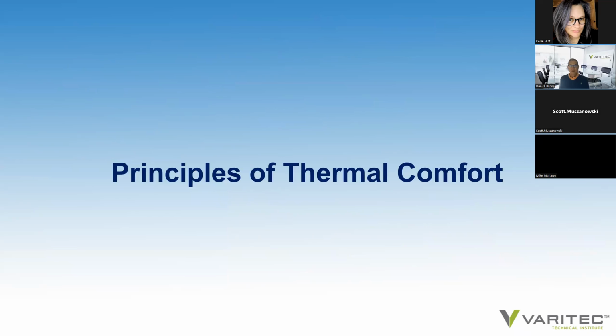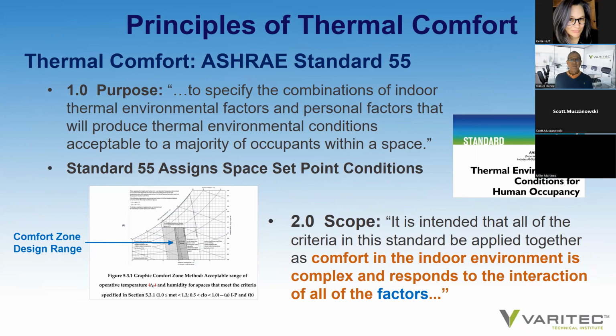So, that being stated, what are these principles of thermal comfort that ASHRAE Standard 55 promotes? Well, Standard 55's purpose in the opening documents of the standard states that its purpose is to specify the combinations of indoor thermal environmental factors and personal factors that will produce thermal environmental conditions acceptable to a majority of occupants within a space. Standard 55 assigns space set point conditions that are adopted by various standards. And Standard 55 scope is intended that all the criteria in this standard be applied together, as comfort in the indoor environment is complex and responds to the interaction of all of the factors.